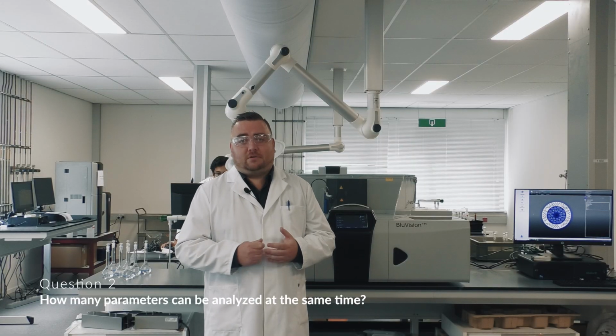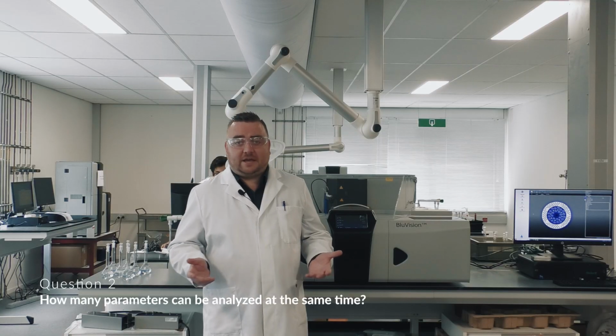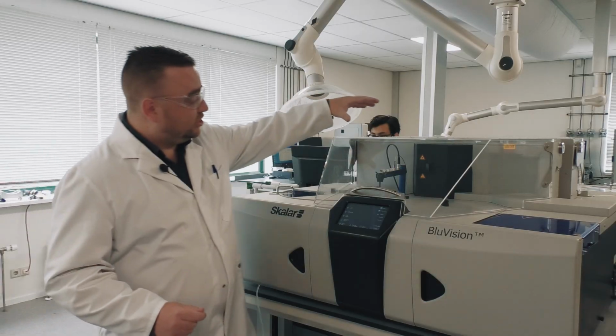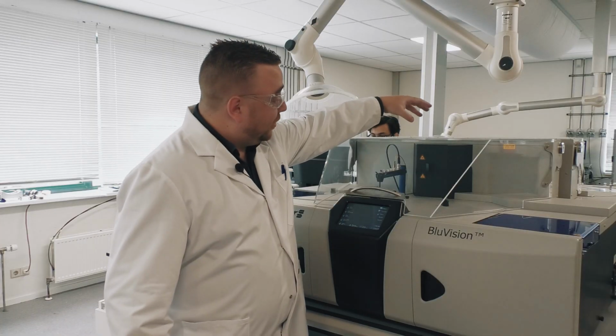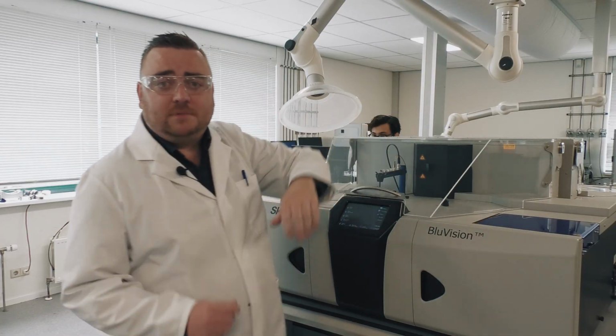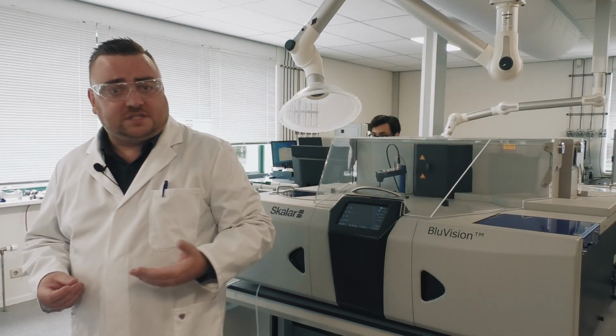Okay, so moving to question number 2, how many parameters can be analyzed at the same time? So the answer to that question is actually a function of the available filters for a particular measurement.